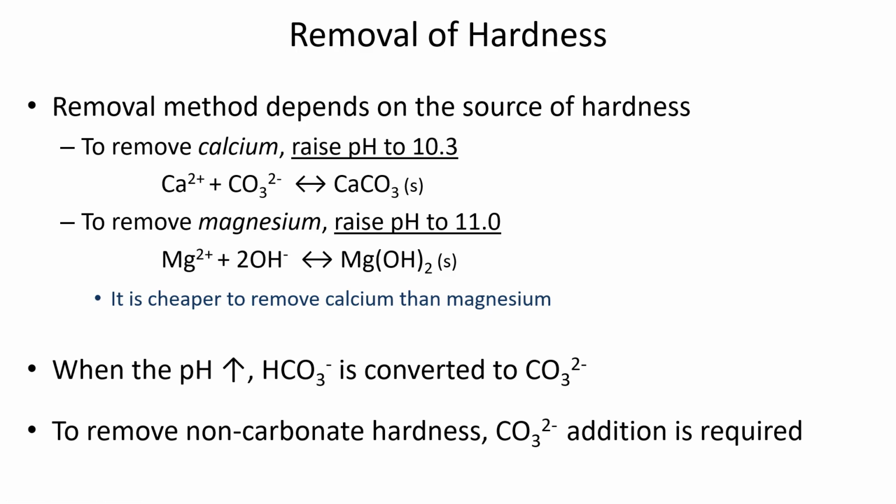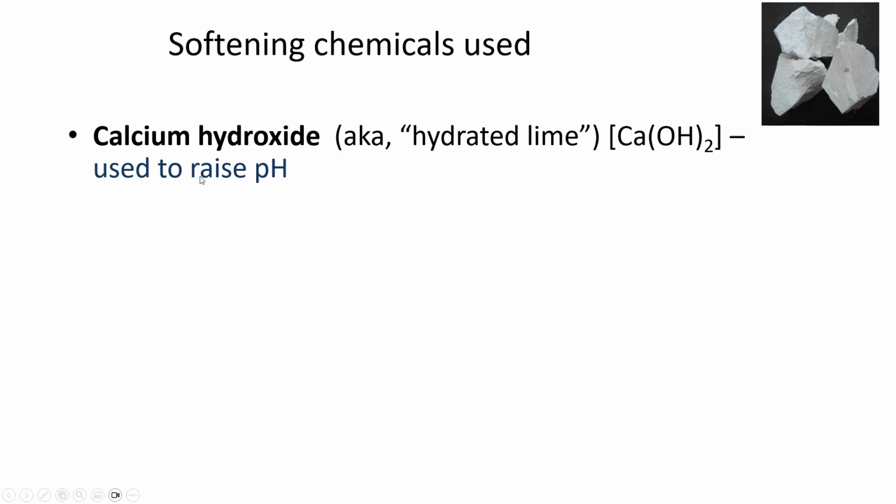The thing we're trying to get out of the water is calcium, but the way we get it out is by adding a different kind of calcium that increases the pH and causes the precipitation of calcium carbonate. The other thing that's counterintuitive is that sometimes we have to add carbonate so that there can be an anion for the calcium ion, which is positively charged, to latch onto.